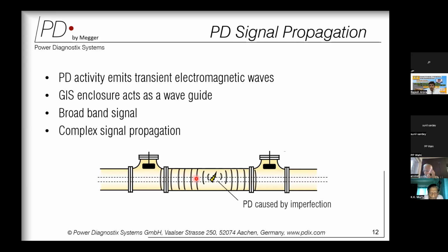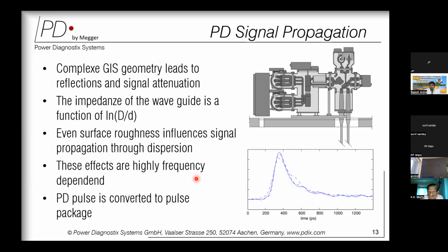Now, these signals are broadband signals, and when this signal passes through the GIS, it generates complex signal propagation. When we say complex signal propagation, it is because in the earlier diagram we saw the GIS as a very good waveguide with a very good structure, like a simple straight highway. But that is not the case when we talk about the real geometry of the GIS. It is similar to what we see on the top right of the diagram. It has a complex structure inside those gas insulated switchgear tubes, and they basically provide various reflections and signal attenuation when the emitted signal passes through different portions of the GIS.